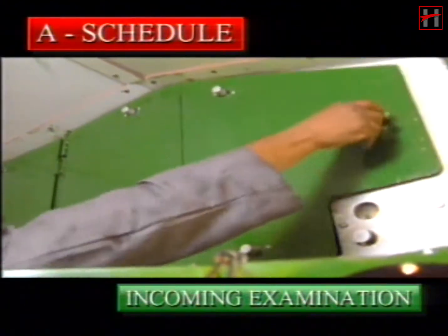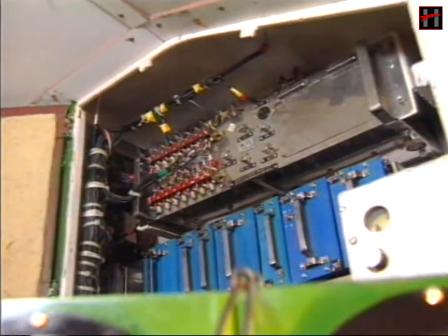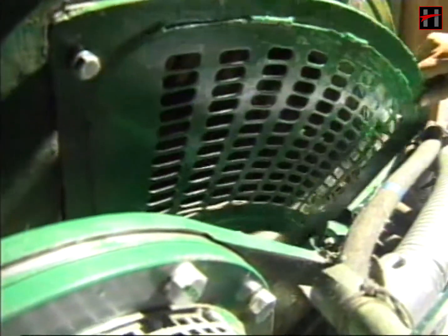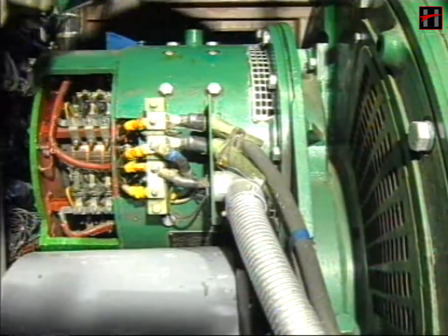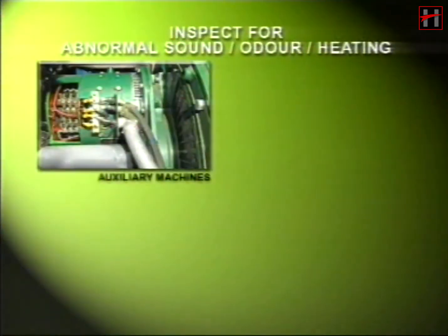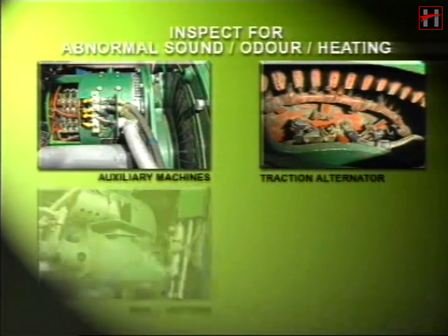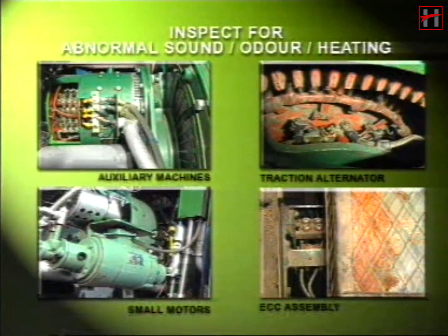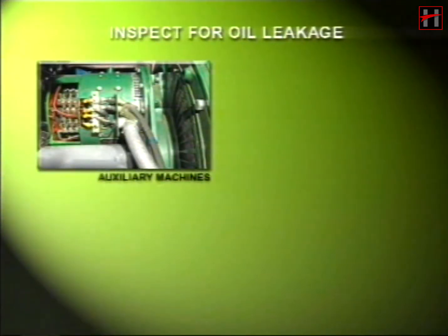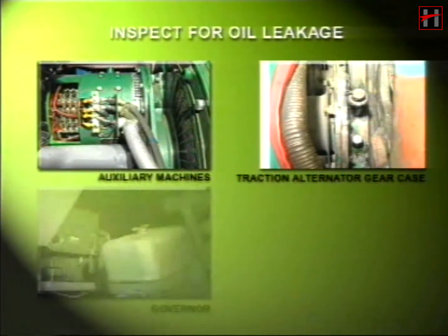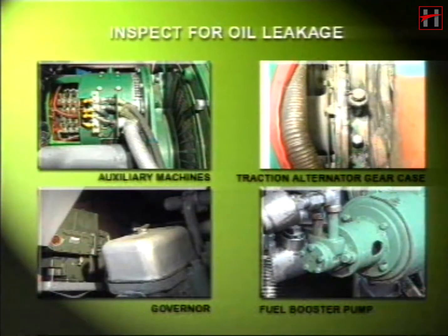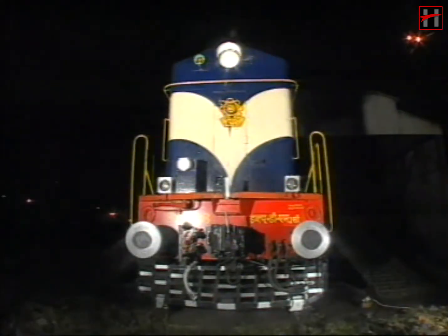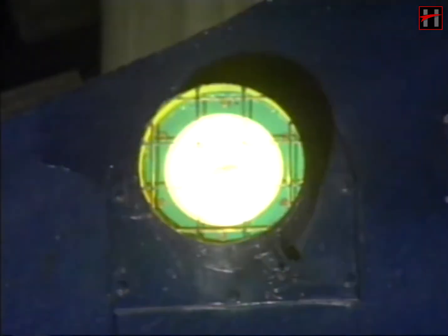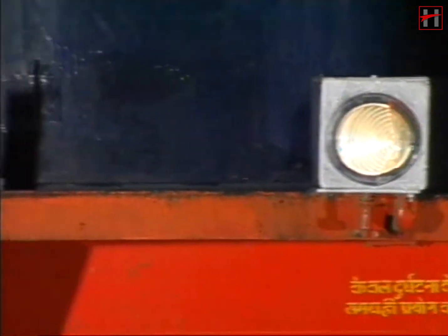In the A schedule of incoming examination, open the covers of the front panel, back panel, control stand, the covers of traction alternator and the auxiliary machines for inspection. Inspect the auxiliary machines, traction alternator, small motors and the eddy current clutch assembly for any abnormal sound, abnormal odor or abnormal heating in the loco run condition. Also, check for any oil leakage from the auxiliary machine, traction alternator gear case, governor or the fuel booster pump. Check the headlights, flasher lights and the marker lights for their proper working.